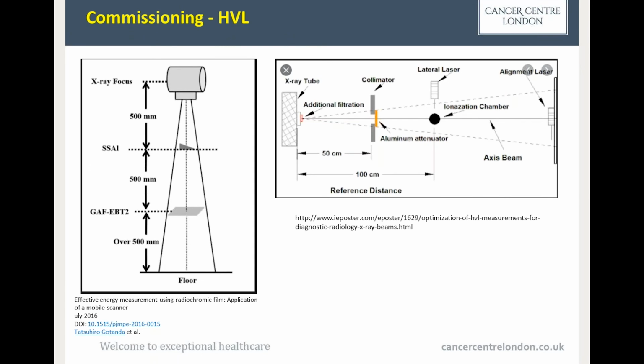And when we got the final documents and could confirm that we could start our verification, we started commissioning, beginning with identification of energies, measuring HVL. It is how energy is represented or expressed. It is by half value layer. It means the thickness of material, mainly aluminium and copper, which reduces the dose at the exit or at the measurement point by half. It is information about how energy transmits through this material, and it is an expression of energy.